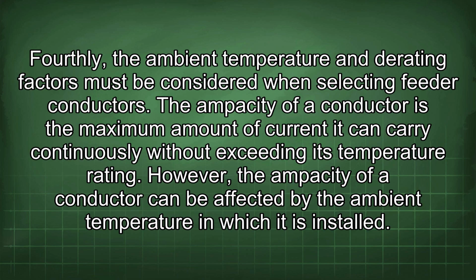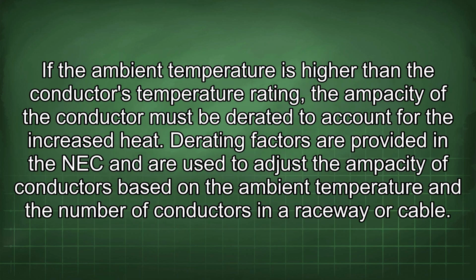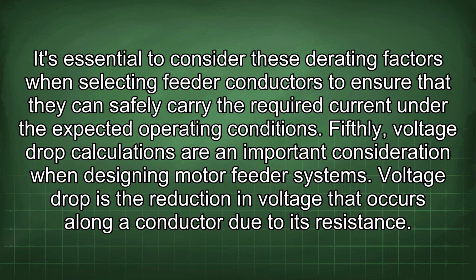The ampacity of a conductor is the maximum amount of current it can carry continuously without exceeding its temperature rating. However, the ampacity of a conductor can be affected by the ambient temperature in which it is installed. If the ambient temperature is higher than the conductor's temperature rating, the ampacity of the conductor must be derated to account for the increased heat. Derating factors are provided in the NEC and are used to adjust the ampacity of conductors based on the ambient temperature and the number of conductors in a raceway or cable. It's essential to consider these derating factors when selecting feeder conductors to ensure that they can safely carry the required current under the expected operating conditions.